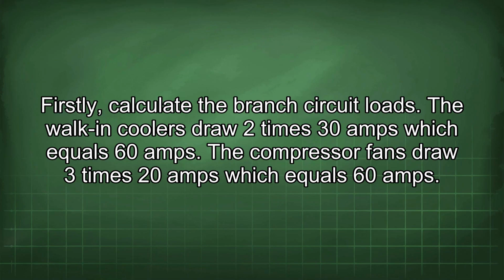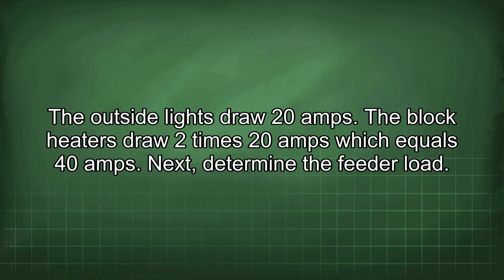Firstly, calculate the branch circuit loads. The walk-in coolers draw 2 times 30 amps, which equals 60 amps. The compressor fans draw 3 times 20 amps, which equals 60 amps. The outside lights draw 20 amps. The block heaters draw 2 times 20 amps, which equals 40 amps.